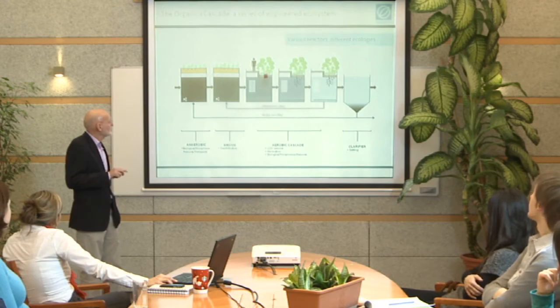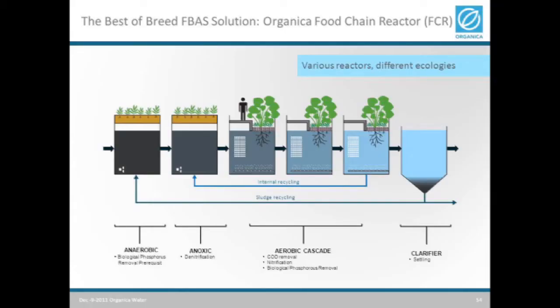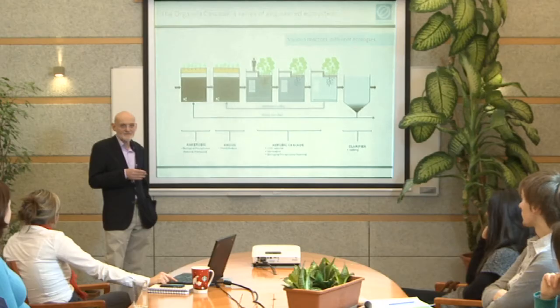The other important aspect, as you can see from the top of the reactors, is the odor question. In wastewater treatment, only certain steps are accompanied by odor — we think all wastewater treatment plants stink, which is not true. If you do the analysis, there are very distinct steps that produce odors. So what we do in design is identify those steps — only two or three — design and build them separately, and treat that air in commercially available off-the-shelf biofilters.